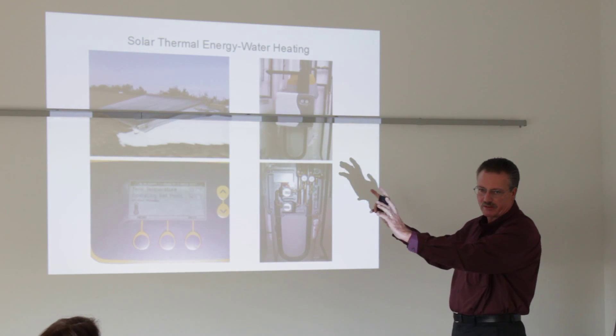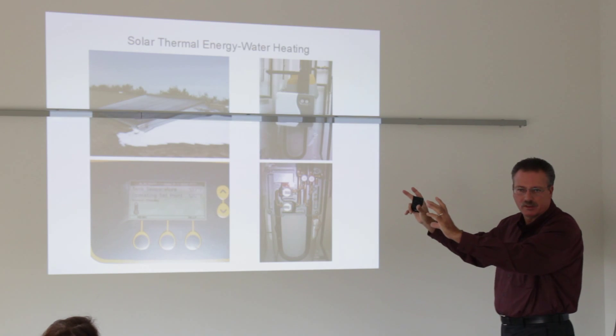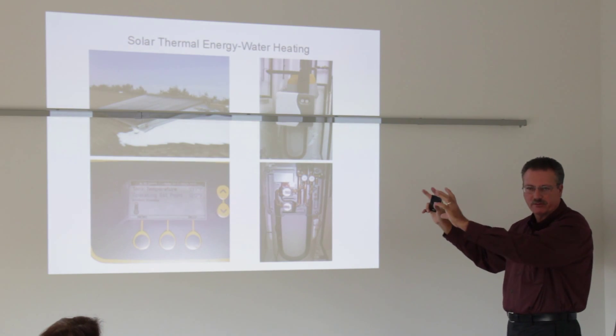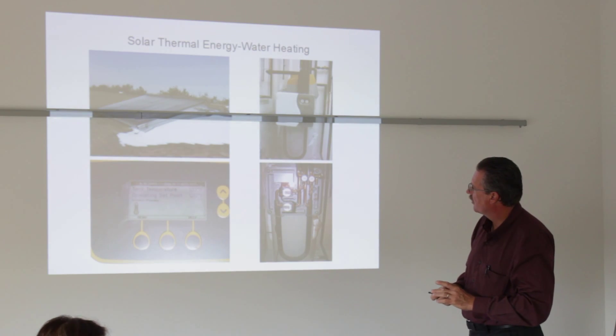Everything can just go right on the side of the water heater. And you can actually use the water heater as a storage tank, so you don't have to have another 80-gallon storage tank. So with the limited amount of space typically available for utility purposes in a home, this is a really nice way to go.